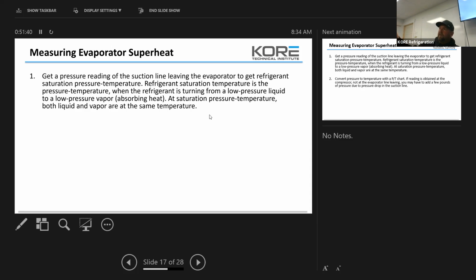Now, evaporator superheat and compressor superheat, it's the same concept, but it's two different readings. What evaporator superheat is telling me is how efficiently I'm saturating that coil and how much heat pickup I'm getting based on the manufacturer specifications at that coil. Compressor superheat tells me how much liquid's coming back to my compressor, because refrigerant-cooled compressors require cool gas. That superheat setting matters because that's what's keeping that compressor alive. It's not the fan blowing across the body of the compressor that helps, but the refrigerant coming in that still has heat pickup properties, picking up heat from the internal of the compressor. So it helps cool the body of the compressor and keeps it running for long periods of time.